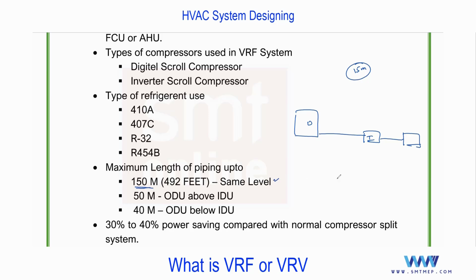Second point, if the outdoor unit is above and the indoor units are below, suppose the outdoor unit is on the roof and the indoor units are connected to multiple floors, say a 5-floor or 7-floor building, in that case the limit is 50 meters. And if it is reverse, for example, the outdoor unit is placed at ground level and connected to multiple indoor units on different floors, with the outdoor unit below the indoor units, in that case we have 40 meters. So this is in general from an interview point of view.